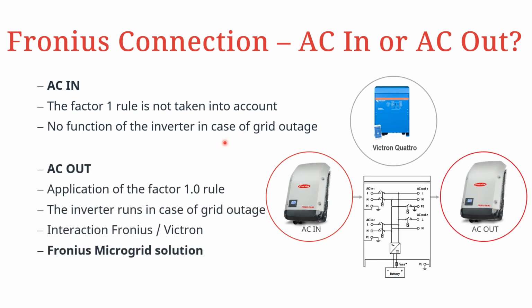The alternative then would be to have the connection of the Fronius inverter to the AC out of the Victron inverter. And in this case, then we have to consider the factor 1 rule. So this then has to be your guiding factor to be able to know how big of a PV inverter capacity should be used in that kind of setup. The benefit here is that if the grid fails, in the case that you have a grid connection, then the Fronius inverter is still able to operate because the battery inverter is able to sustain the operating voltage and frequency. So in this case, we have talked about already the interaction between the Fronius and the Victron inverter through frequency drop. And this is now what we refer to as the Fronius microgrid solution.